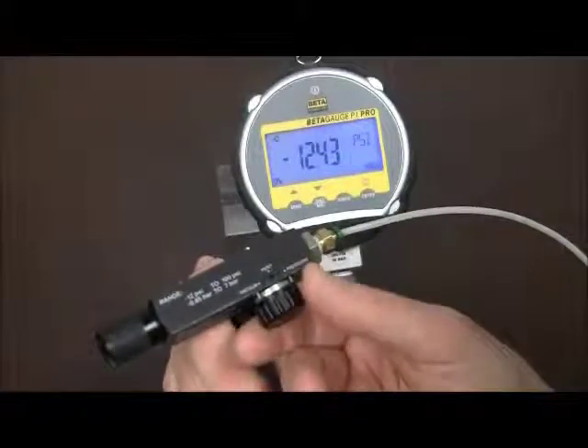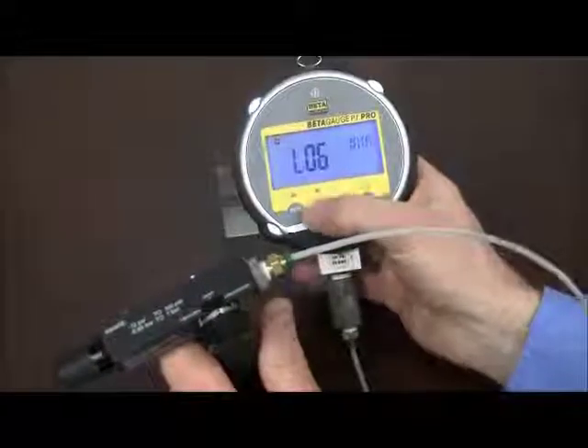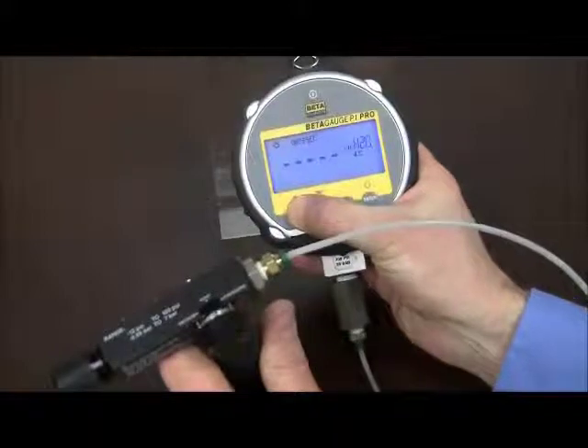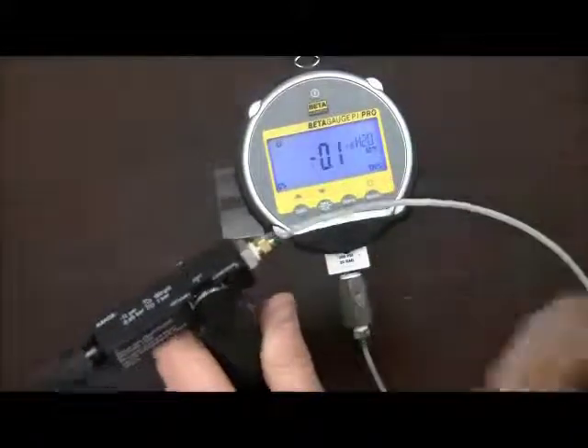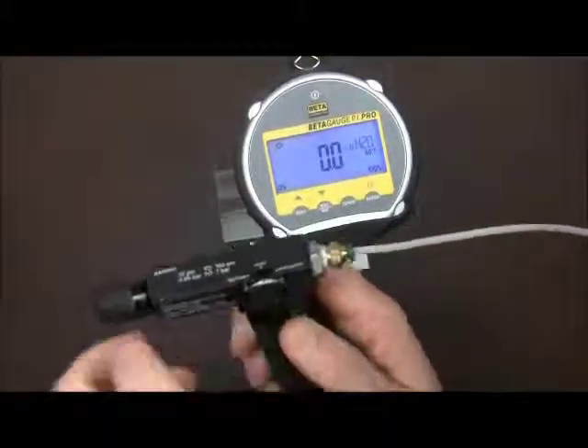How about inches of water? So let's vent. Set our gauge to inches of water. Let's go to pressure.